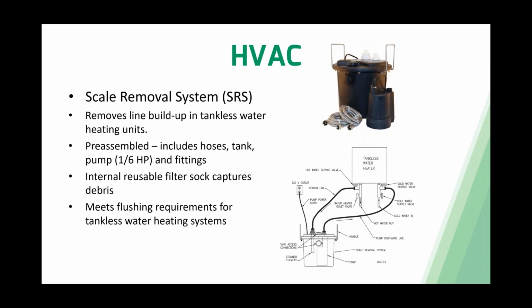The next thing within the HVAC is our scale removal system, what we call the SRS. You'll see in the bottom right-hand corner, it's used for tankless water heaters and it removes the lime buildup within the tankless water heater units. That's a quick little diagram of how it's set up, and you'll see a package of it up at the top right-hand corner. It is pre-assembled. It comes with the hose, the tank, and one of our Flood Sucker series, which is a 1/6 horsepower pump, and it includes the fittings as well as an internal reusable sock that captures the debris that is in there. One thing to note is that it does meet the flushing requirements for tankless water heater systems where these systems are used.